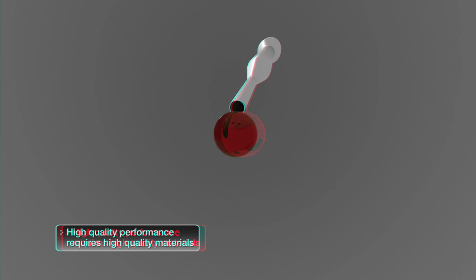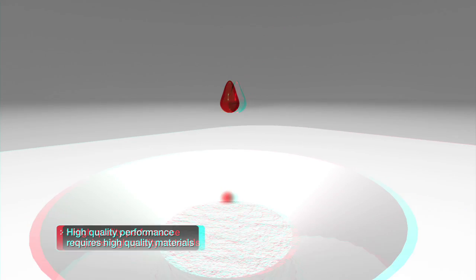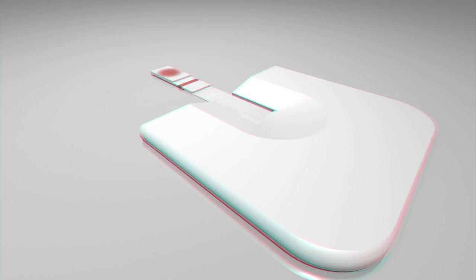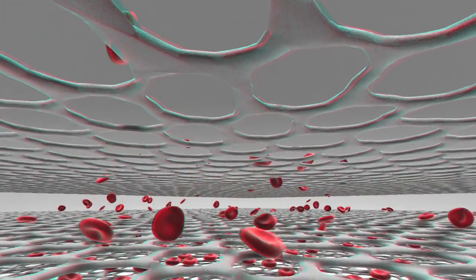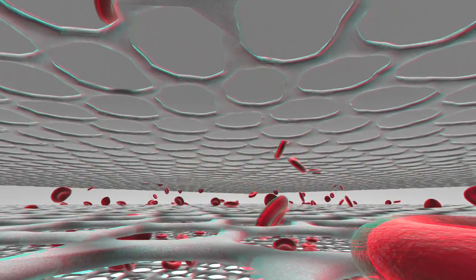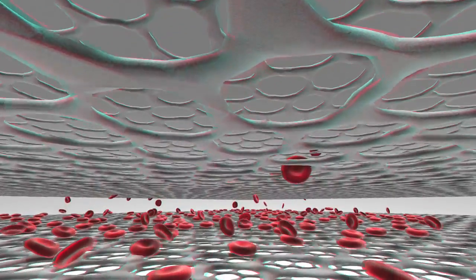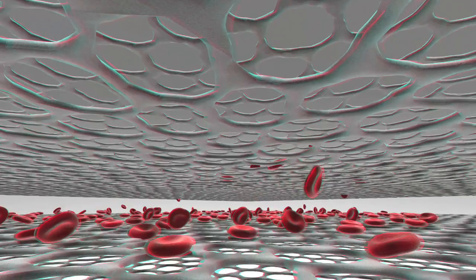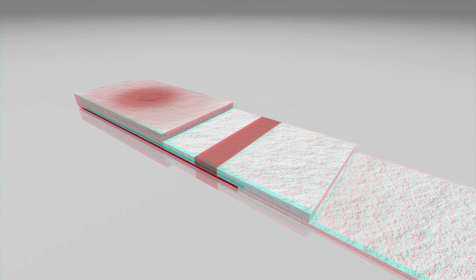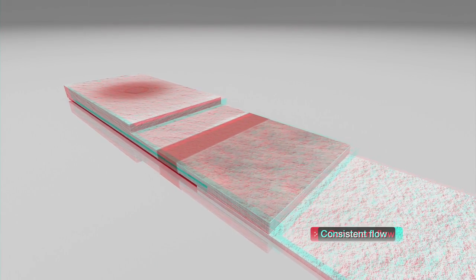To demonstrate the benefits of using good gold, in a typical lateral flow device, a blood sample is deposited into the well and filtered through a series of membranes to remove blood cells, leaving plasma to arrive on the conjugate pad, reconstituting the gold conjugate. Through capillary action, the conjugate is drawn through the membrane. The monodisperse gold flows easily and consistently.